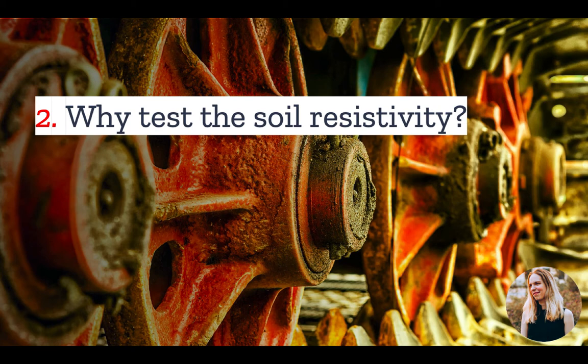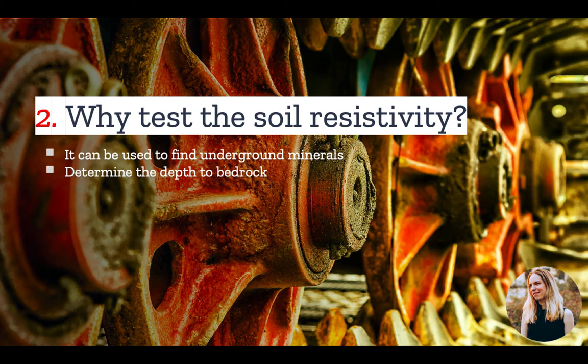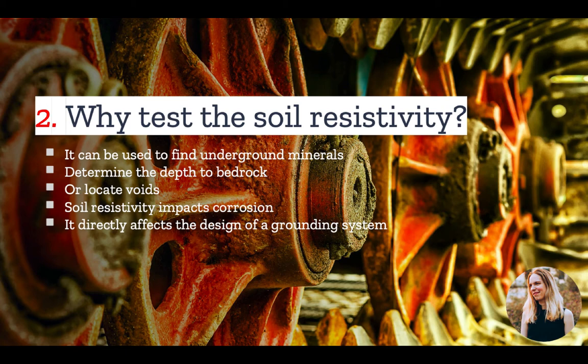Number two: why test soil resistivity? Well, the soil's resistance to electrical current can help you determine a number of things, such as the location of underground minerals, bedrock, and voids. In addition, soil resistivity affects the degree of corrosion in buried pipes and has a direct impact on the materials and treatments you must use when installing underground structures or pipes. Soil resistivity also affects the design of grounding systems, such as when installing an electrical substation or lightning protection. And finally, soil resistivity is a good proxy for moisture content, which can have a number of applications, especially in an agricultural context.